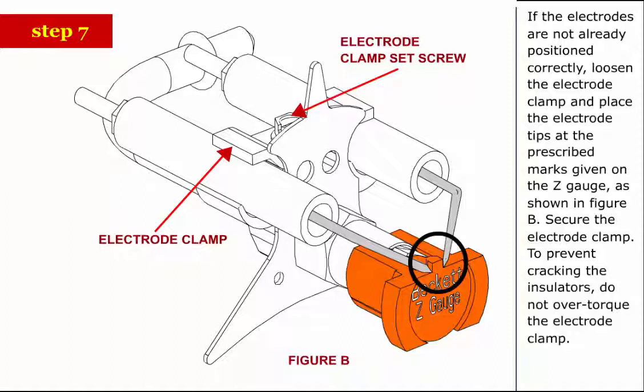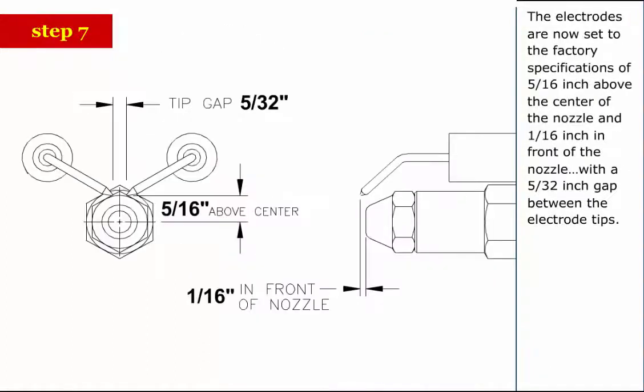To prevent cracking the insulators, do not over-torque the electrode clamp. The electrodes are now set to the factory specifications of 5/16 inch above the center of the nozzle and 1/16 inch in front of the nozzle with a 5/32 inch gap between the electrode tips.